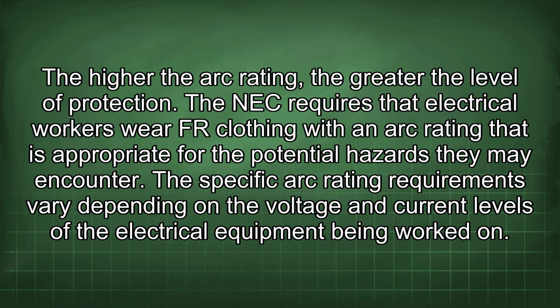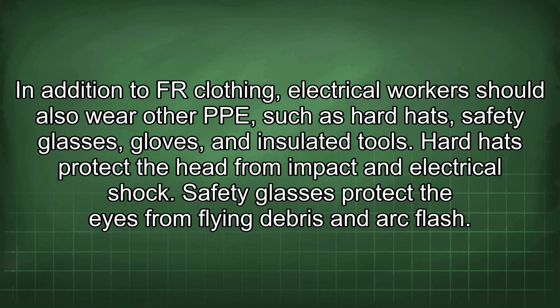The NEC requires that electrical workers wear FR clothing with an arc rating that is appropriate for the potential hazards they may encounter. The specific arc rating requirements vary depending on the voltage and current levels of the electrical equipment being worked on. In addition to FR clothing, electrical workers should also wear other PPE such as hard hats, safety glasses, gloves, and insulated tools.